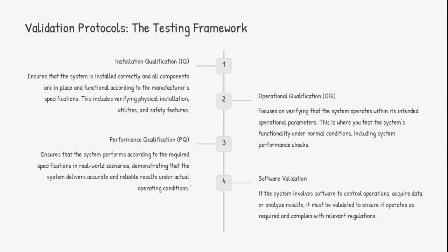Validation protocols form the testing framework, including installation qualification, IQ, operational qualification, OQ, performance qualification, PQ, and software validation. IQ verifies the system is installed correctly and functioning as intended. OQ focuses on verifying the system operates within its intended parameters. PQ ensures the system performs according to required specifications. Software validation ensures systems relying on software operate as required and comply with regulations.